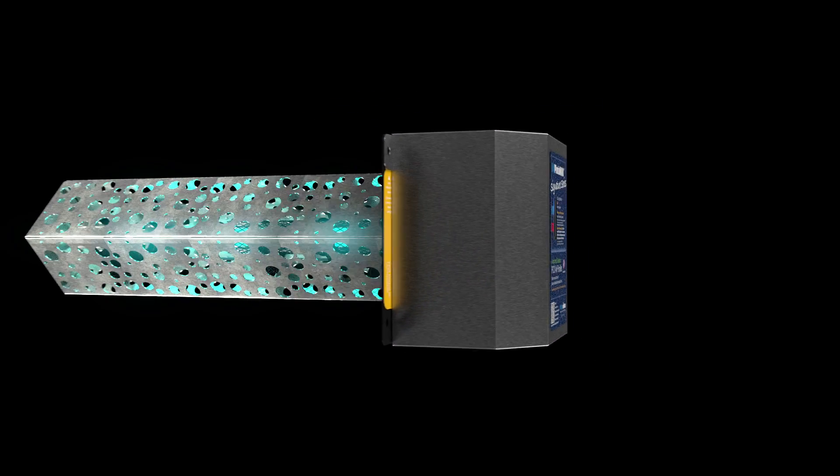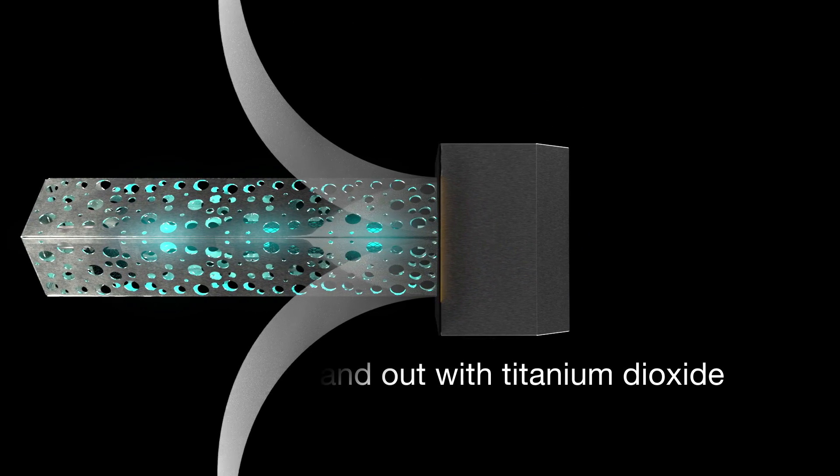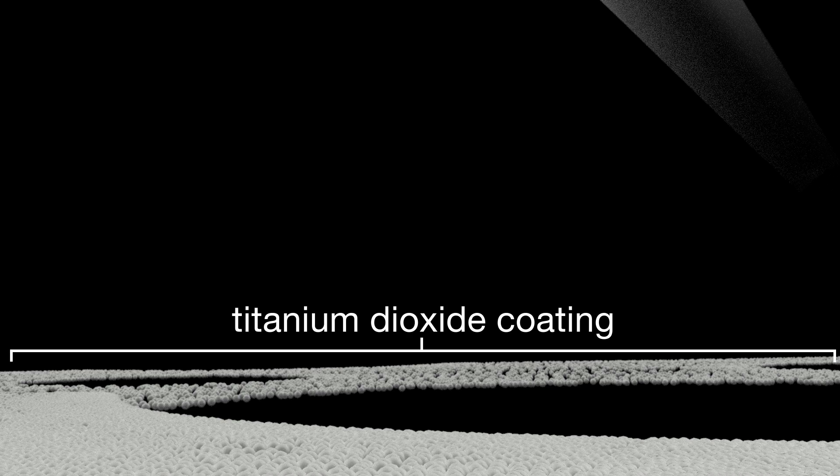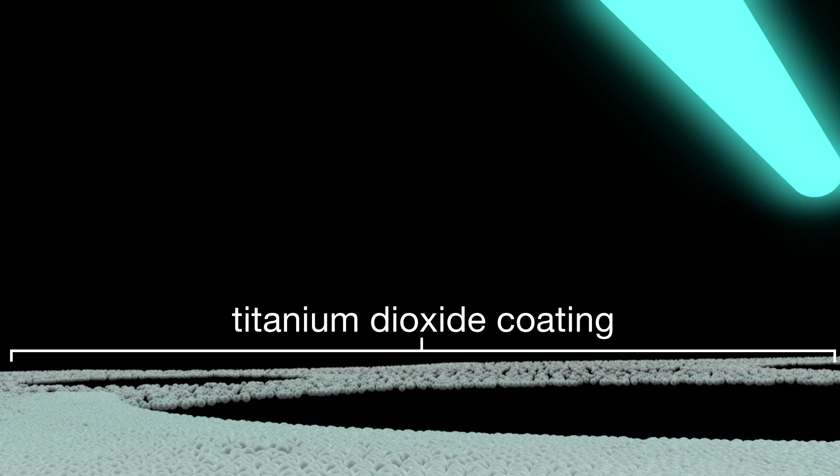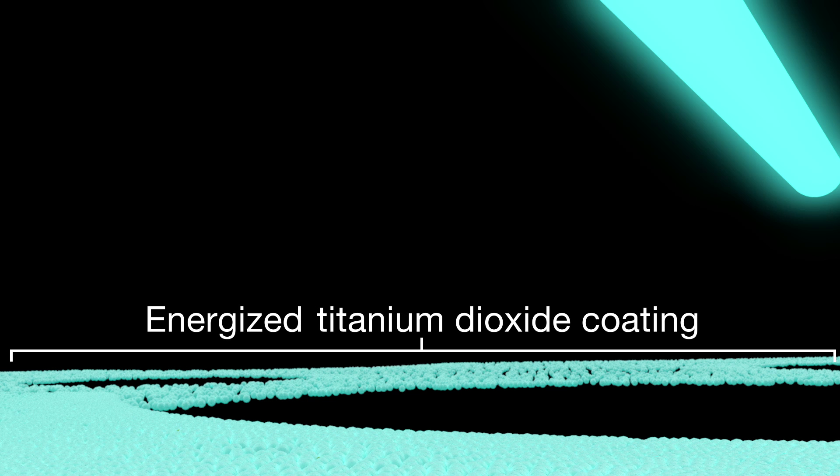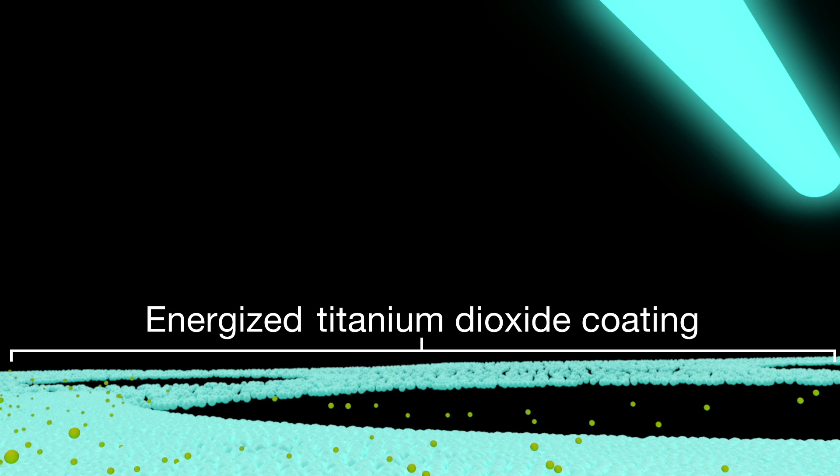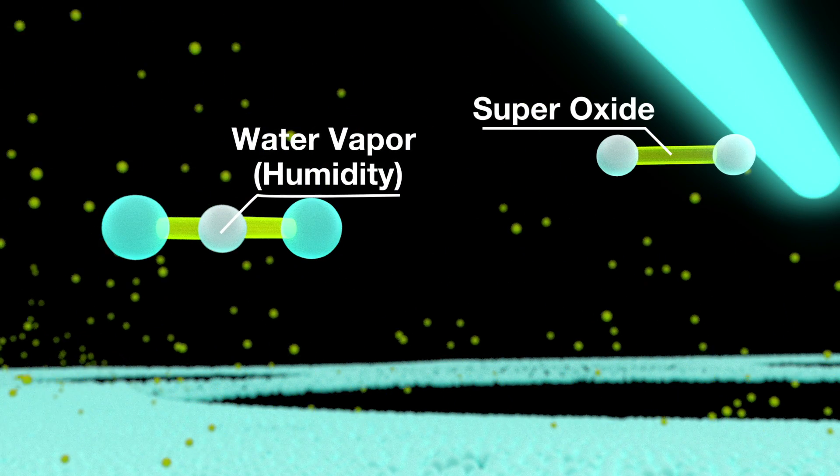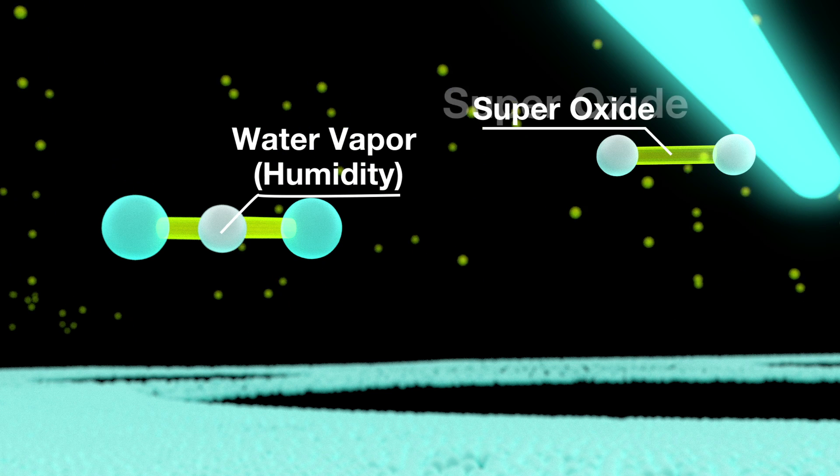The UV Photomax Advanced Oxidation Module is coated with an exclusive titanium dioxide formulation. When UV light is applied to the surface, the titanium dioxide coating becomes energized, causing it to release electrons. The electrons then combine with oxygen to create what are known as super oxides.